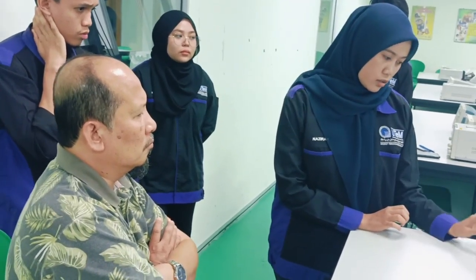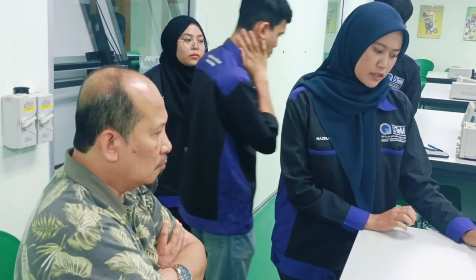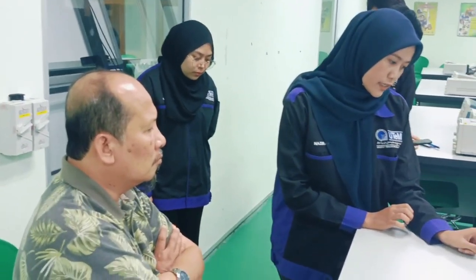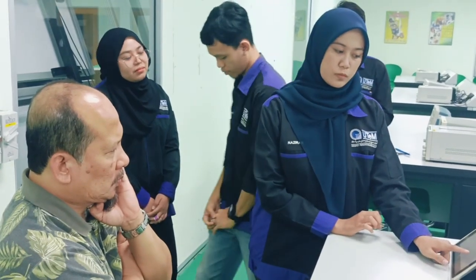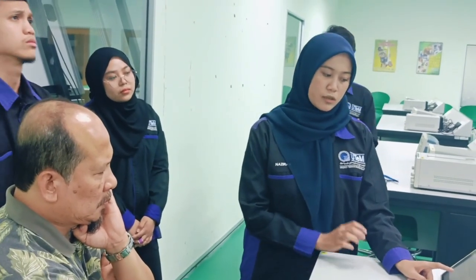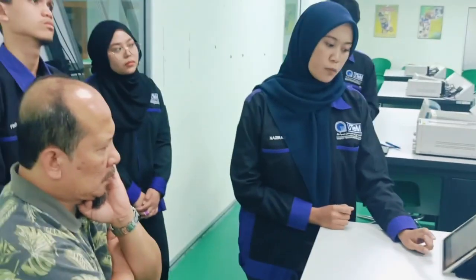The resistance values fluctuate but frequently stay within a relatively narrow range between 211 and 326 ohms, between 6 meters and 9 meters. However, there is a significant drop in resistance at 40% distance, which is 6 meters, the outlier, and the result we get at 40% is 211 ohms. Next, the cause may be soil conditions, conductive objects, or measurement errors.